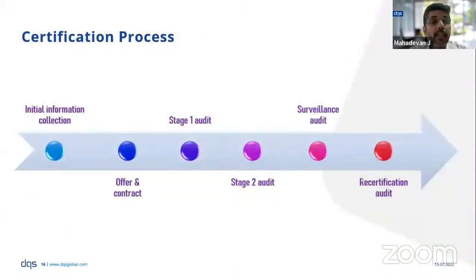So in a nutshell, this is how the process works. First, initial information collection. Any certification body will collect the initial information from the manufacturer in order to determine the effort required in the assessment. This includes identifying the products being covered, the scope of the certificate, what locations need to be covered, what processes are covered in each location, and how many employees are involved. Based on all these factors, the number of days required for the audits is estimated. And then a commercial agreement is entered into with the manufacturer. Then comes the stage 1 audit, which is a preliminary document review assessment to see the readiness of the organization for certification.